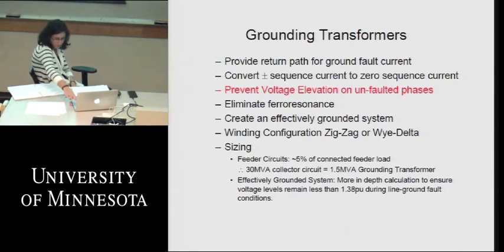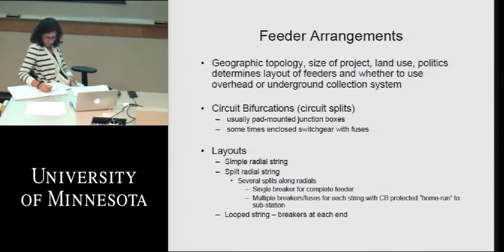Next slide, then. The different feeder arrangements, as you quickly saw on that single line diagram here, really the geography dictates a lot of how the project is going to look, where we're going to put wind turbines, and we do what we call wind siting to optimally place the wind turbines for the wind. And in doing so, this dictates how they're going to get connected by the cabling in between them. So those feeder circuits go out, they split in these bifurcations. It can be done at the wind turbines themselves, or it can be done at junction boxes. It could be done at switchgear also. Different companies do it different ways.